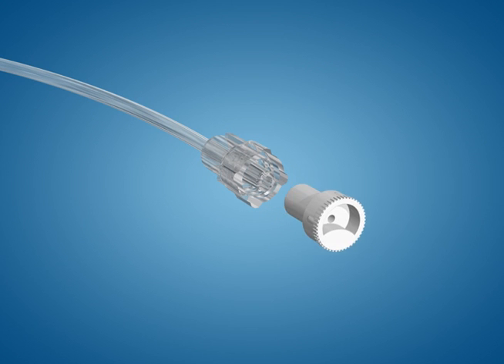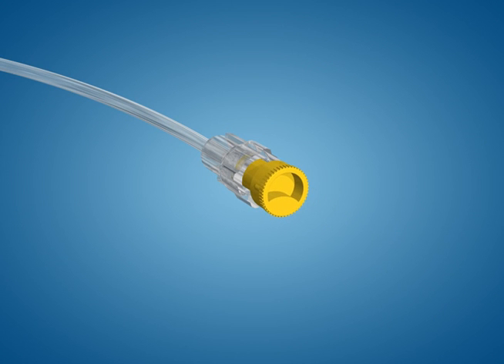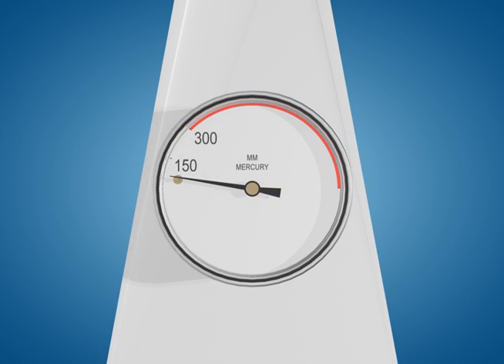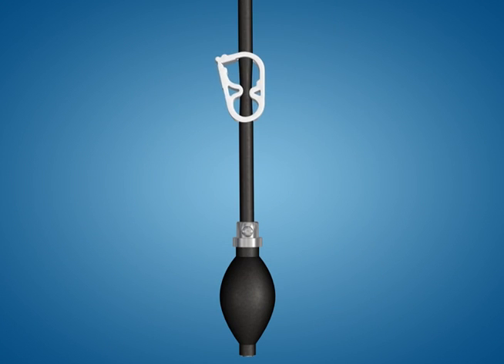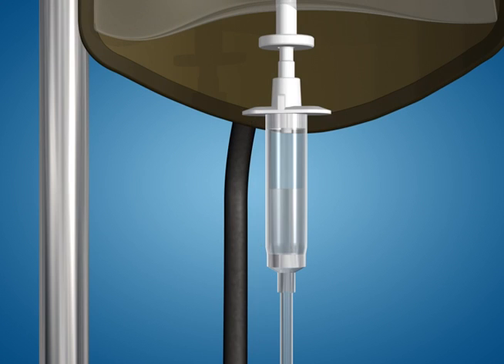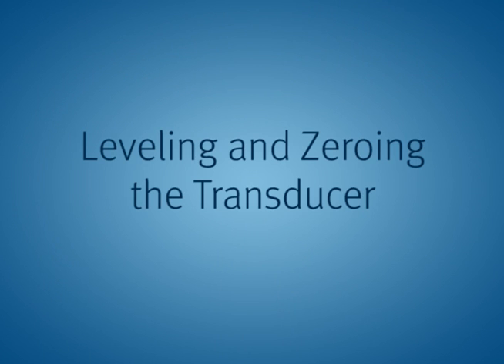Remove the vented cover at the patient connector and flush the rest of the patient line. Place a non-vented cover onto the patient connector. Now pressurize the solution bag to 300 millimeters of mercury. Close the pressure cuff clamp. Make certain the drip chamber does not completely fill during pressurization so that you can verify fluid flow and line patency. Leveling and zeroing the transducer.